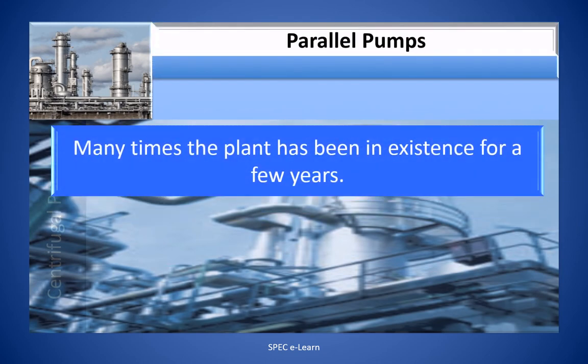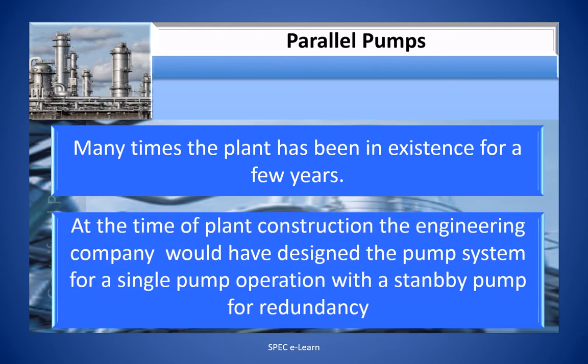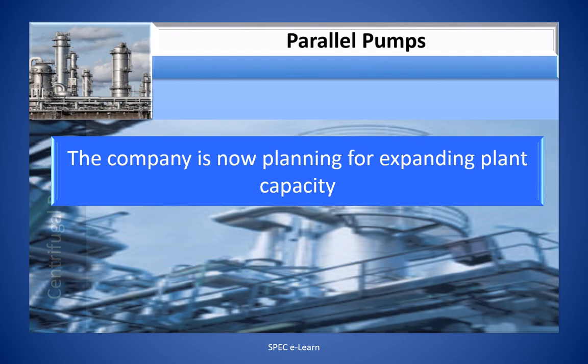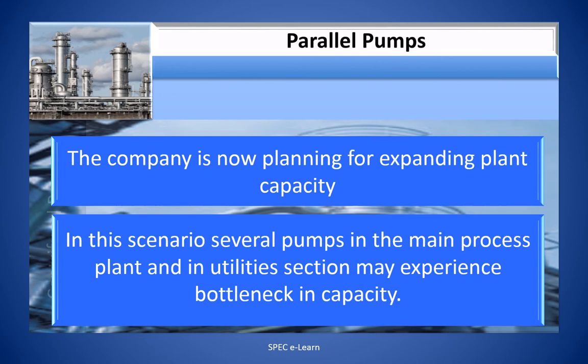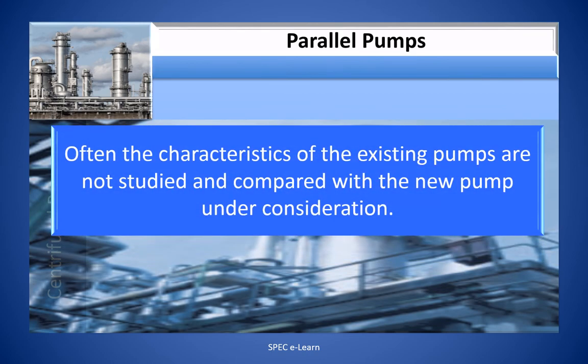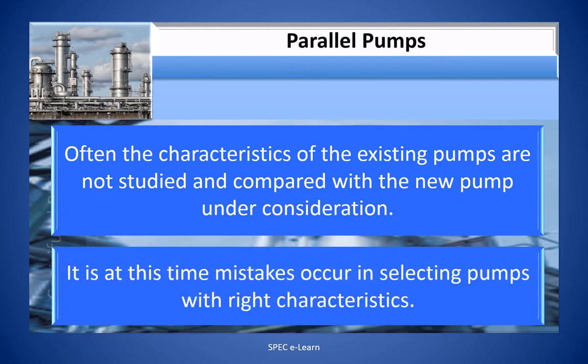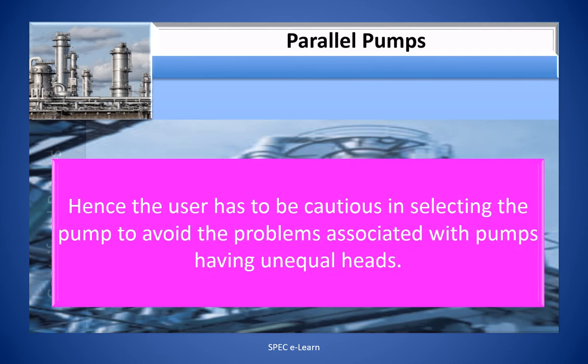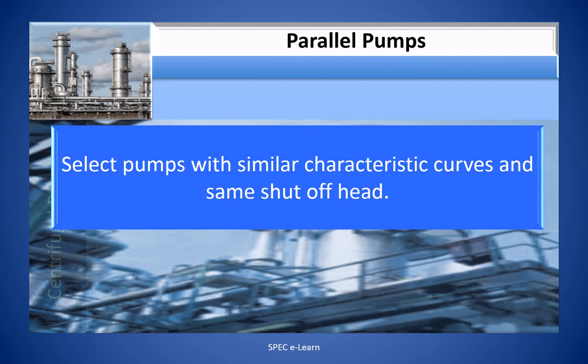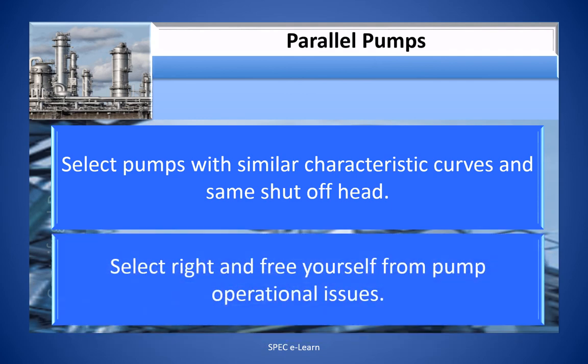Many times, the plant has been in existence for a few years. At the time of plant construction, the engineering company would have designed the pump system for a single pump operation with a standby pump for redundancy. The company is now planning for expanding the plant capacity. In this scenario, several pumps in the main process plant and in utility section may experience bottleneck in capacity. Often, the characteristics of the existing pumps are not studied and compared with the new pump under consideration. It is at this time mistakes occur in selecting the pumps with right characteristics. Hence, the user has to be cautious in selecting the pump to avoid the problems associated with pumps having unequal heads. Select pump with similar characteristic curves and same shut-off head. Select right and free yourself from the pump operational issues.